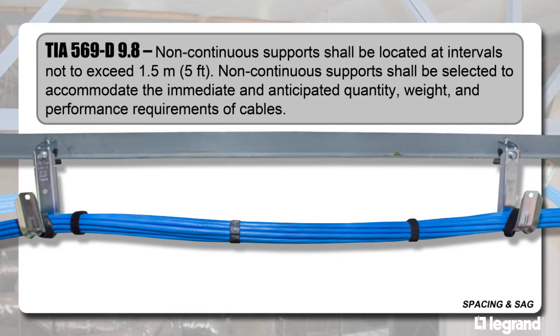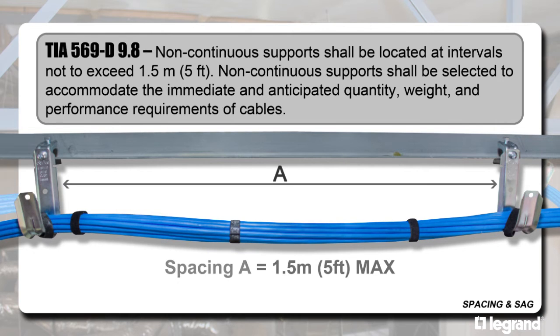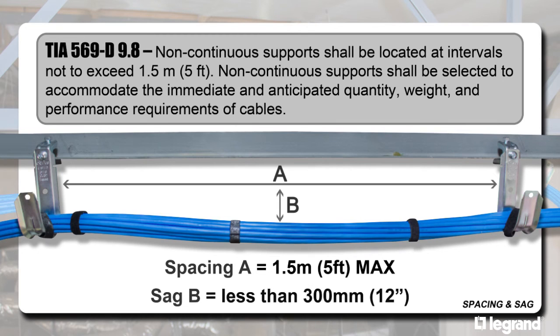The maximum allowable spacing between cable supports is about five feet. The cable tension should allow for no more than about a foot of sag between each support. It is best to stagger the spacing on a long run to prevent harmonic interference or crossover.